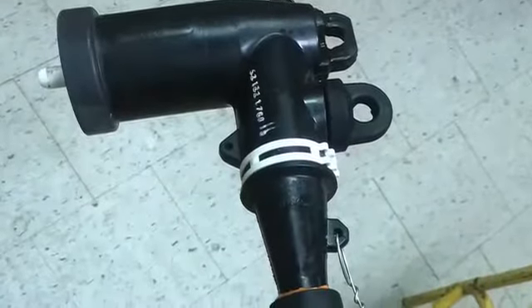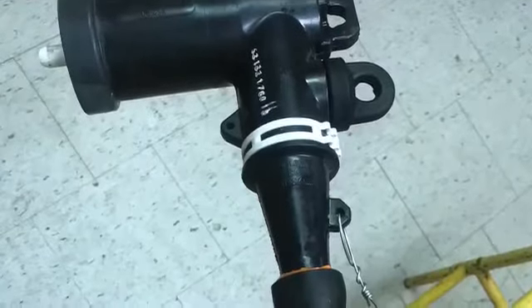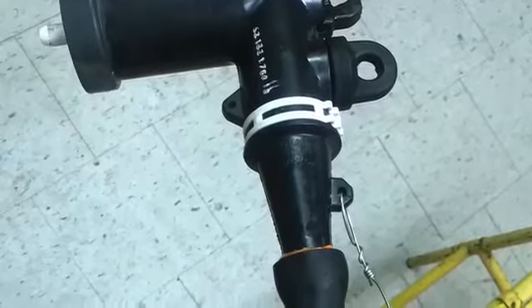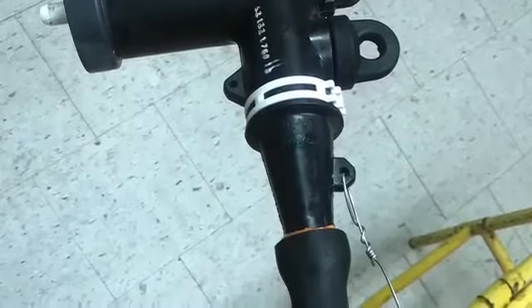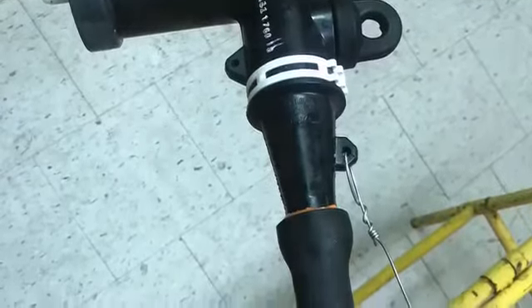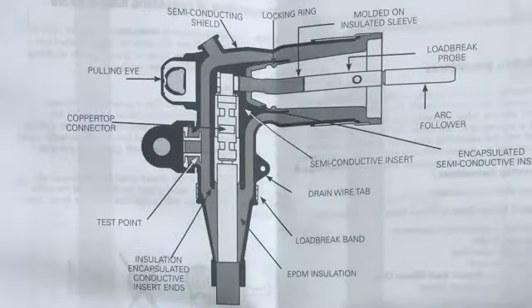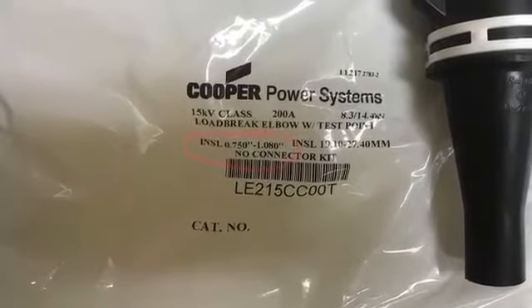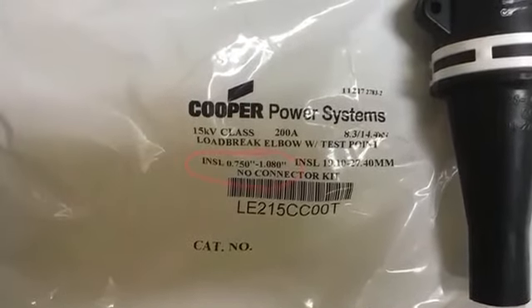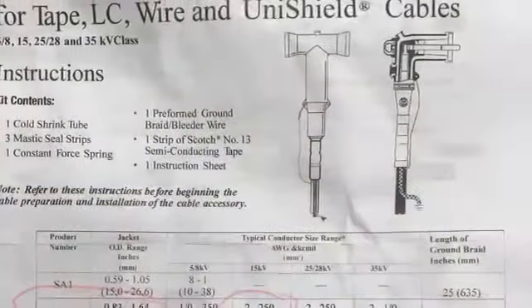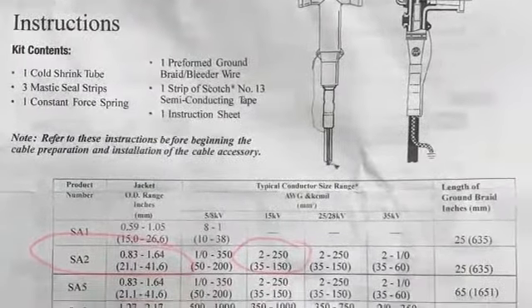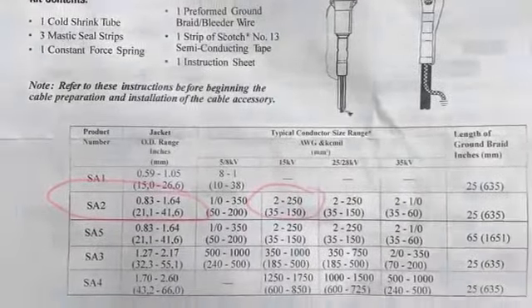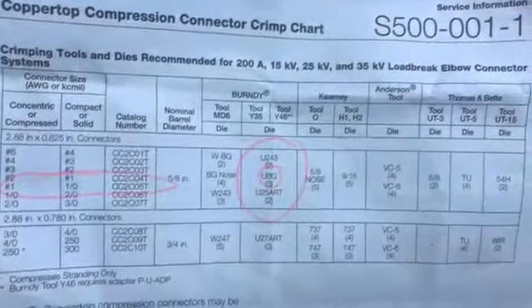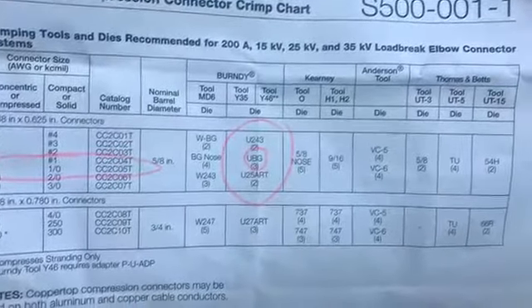In this video, I'm going to demonstrate how to install a Cooper 200 amp loadbreak elbow on a 1-aught compact copper tape shield EPR medium voltage cable. Some things to verify before you begin the installation of the termination is that you have a compatible termination for the cable that's being installed, you have a compatible shield adapter kit for the termination, and that you have the appropriate size lug as well as the dies for crimping the lug.